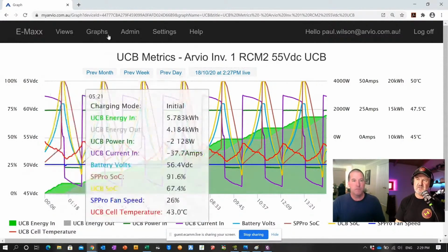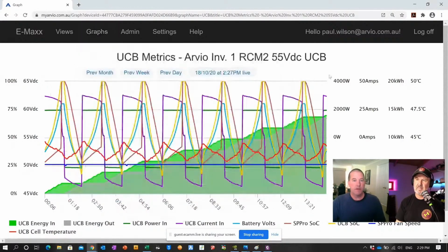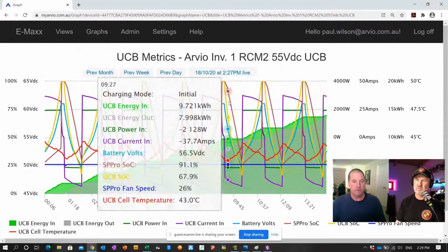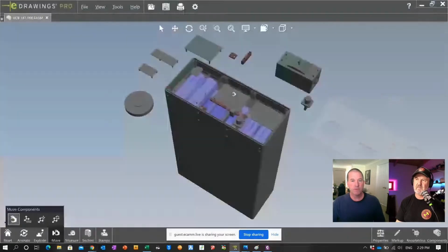So you're building larger units, the shipping container sized? Yeah, well, it's including 250 kilowatt hours of storage using this module. Wow. So there's 42 of these modules inside the container, along with 6 SP Pros, the 1202, which is the 20 kilowatt model, and we're hitting 214 kilowatts peak AC and 120 kilowatts continuous AC from the inverters, and the battery energy storage of 250 kilowatt hours is, from a power point of view, on a DC side, you're looking at 42 times 37, which is an astronomical number. I think it's 2 megawatts of DC power available if you needed it.